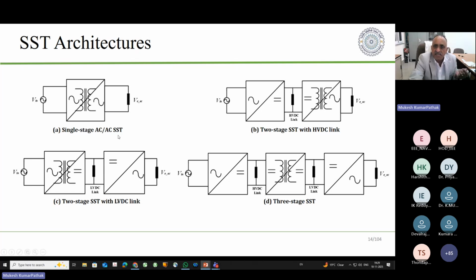This is a single stage AC-AC SST, solid state transformer. The other possibility is to have two stages. The first is to convert this input to a DC supply, so this becomes a high voltage DC link. This DC link will then be applied to the high frequency transformer. That means this DC will be used as an input to this transformer and converted into high frequency AC supply, and from that we tap the output and convert it back to 50 Hertz supply. So this has no DC link. This has AC only: input AC, high frequency AC, and output AC.